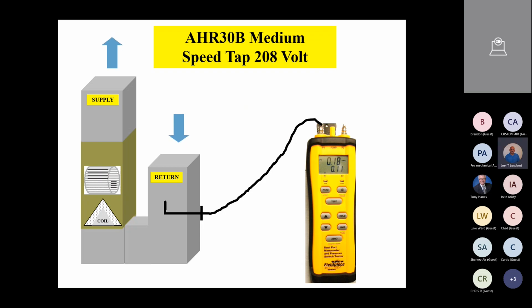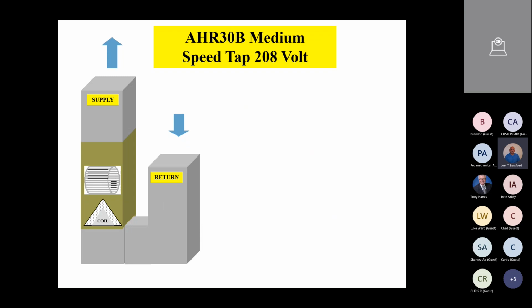I then take those two readings. So I had a 0.32 and a 0.18. And so let's add those up. Again, write that down or just remember it. I then add those values together. So the external static pressure is going to be 0.32 plus 0.18 equals a 0.50. Now, guys, this is important. You don't have to do algebra to add these up, even though the 0.32 is a positive pressure and the 0.18 is a negative pressure. You don't have to do algebra and say, well, what's a negative and a positive? No, you just add the whole numbers up.